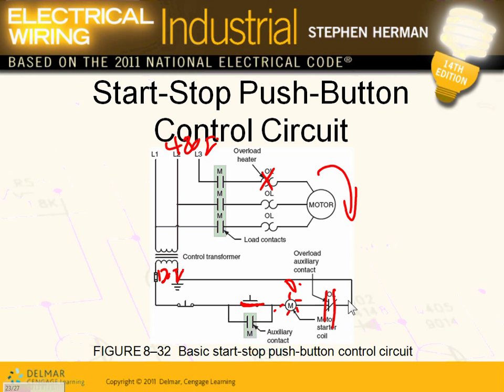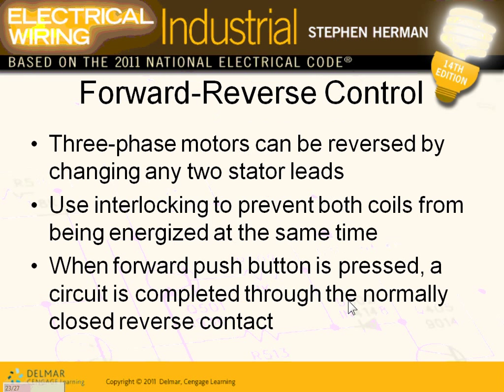The stop button is always in series. The start button is always in parallel with the so-called holding contact. When you energize the coil, you drive the holding contact shut, which bypasses the momentary start push button. As a designer we don't go deep into this, but as an electrical professional it makes you a better designer to understand how the system works — you'll be in situations where you need to analyze it.